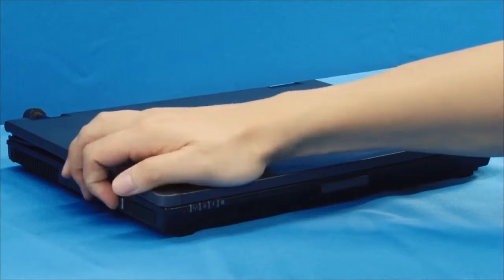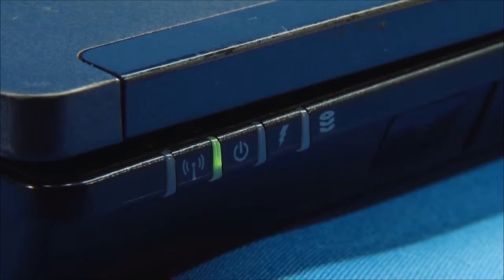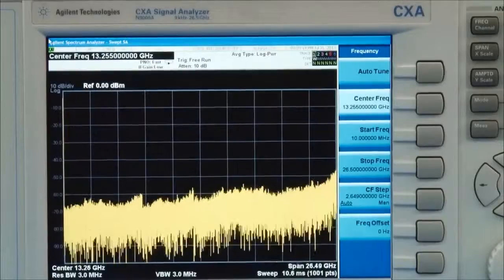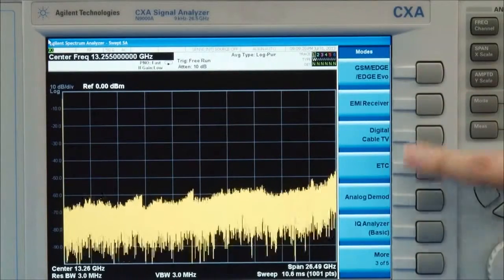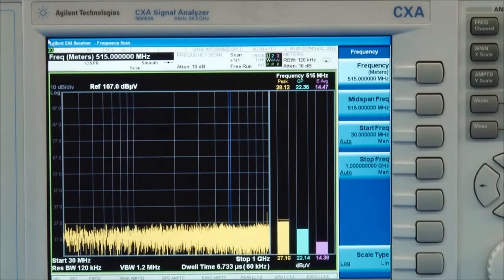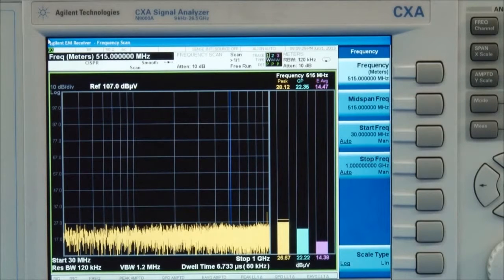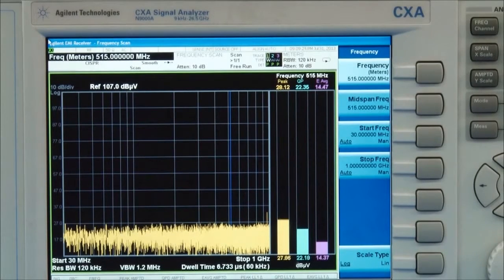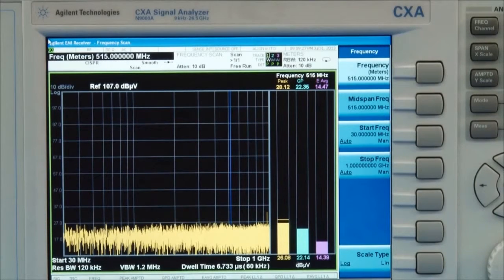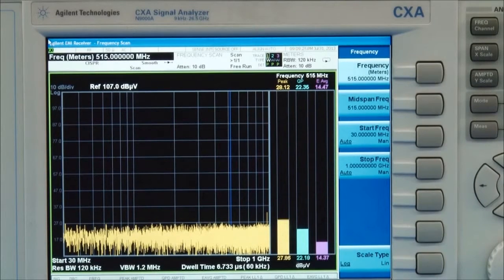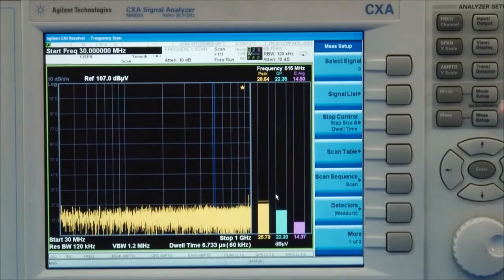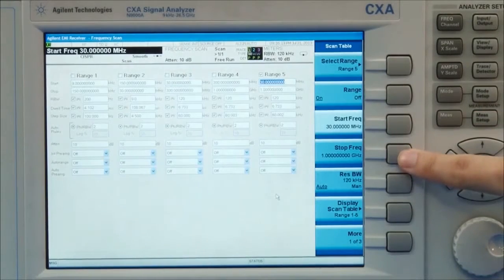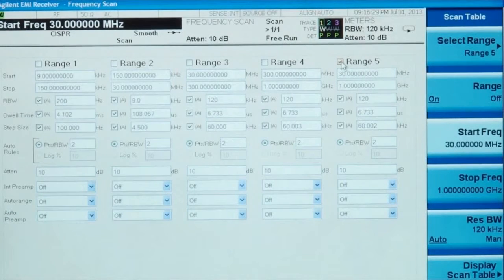For this demonstration, we chose this old laptop computer as our DUT and we need to turn it on. Now let's set the CXA signal analyzer. When we access the EMI receiver mode, the display looks different than when the CXA is in the normal spectrum analysis mode. In EMI receiver mode, the analyzer is able to make CISPR pre-compliant measurements, which has 6 dB bandwidth filters, and selectable EMI detectors including EMI average, quasi-peak and peak detectors. It has predefined test ranges according to EMI standards. Here we chose range 5, 30 MHz to 1 GHz.